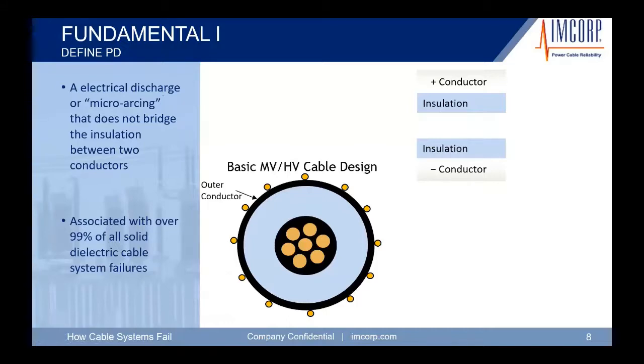We talked about this briefly a minute ago. We have an outer conductor on a piece of cable. Now, the concentric neutral here is an example of concentric neutral versus copper tape shield, what's used in the industrial market. And here we have the inner conductor. We have our insulation, so we're going to install a little void here. So we're going to try to show you what happens from this illustration when you have some partial discharge. So here we have our little air gap, a void in the insulation.